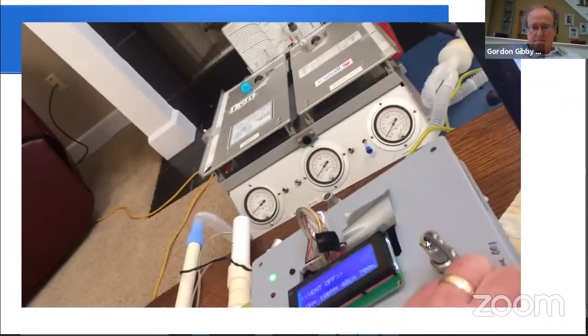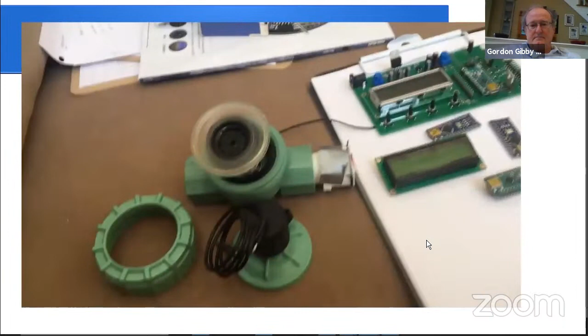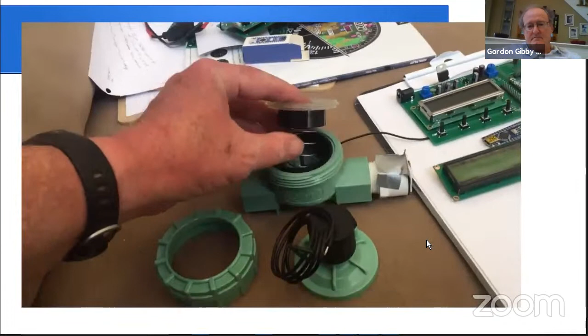I don't know if I can do this, if I'm coordinated enough to do this, but this is one of my prototypes, and it's pretty ghastly how it's wired. You don't want to look at that too close. Over here, I have some examples of how all this is done. This is the expiratory valve, and it's simply an orbit valve that we have moved the spring from the top to the bottom, and I think it's normally closed, and we turned it into normally open. And then we pressure control it by running air into the top.